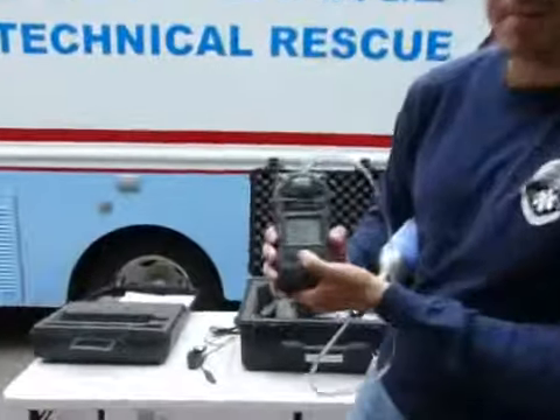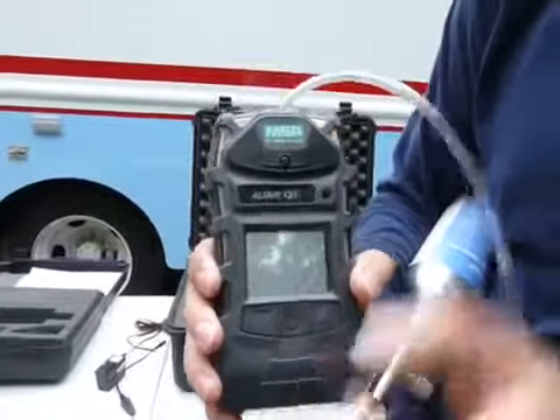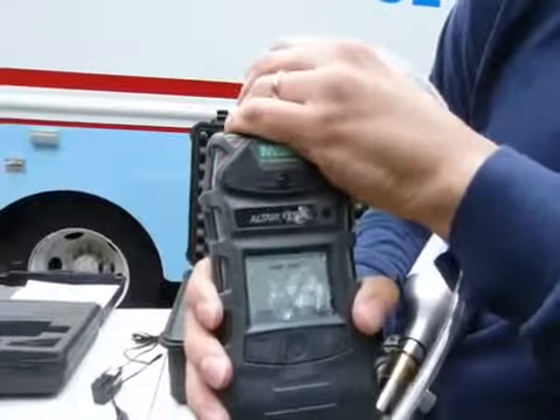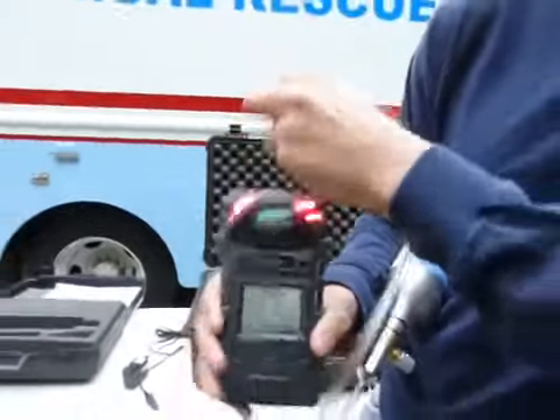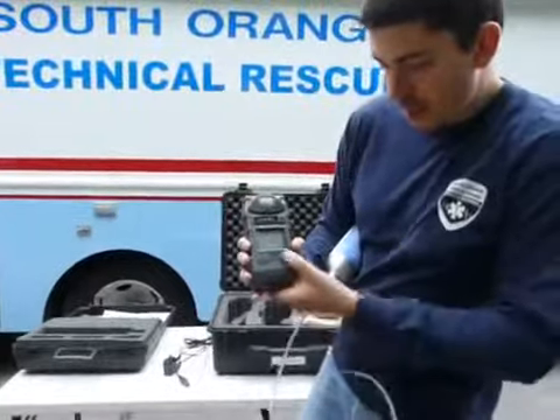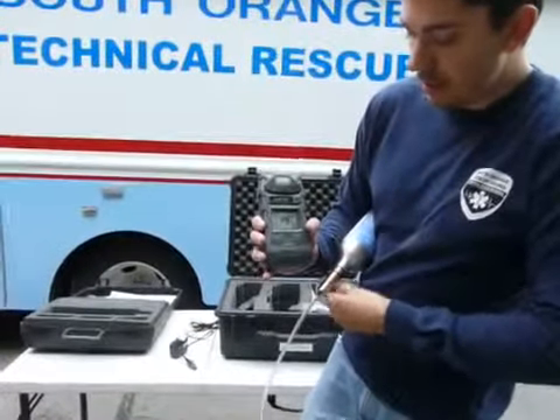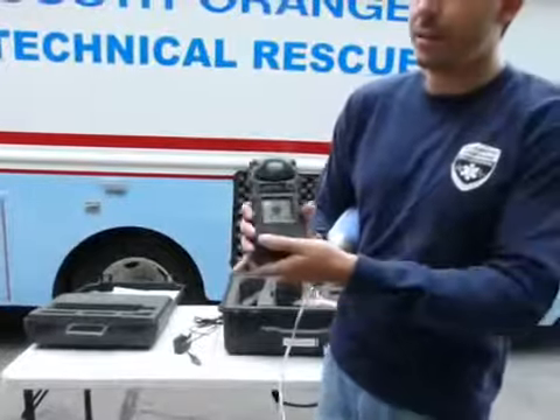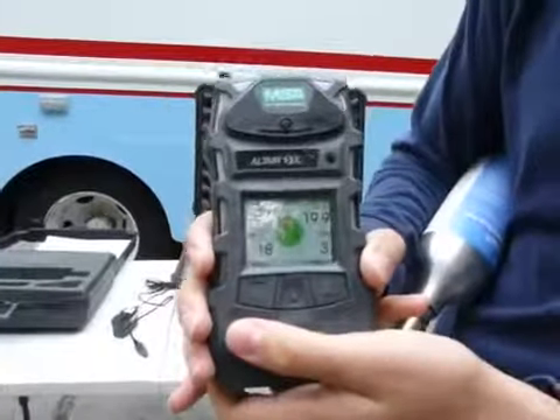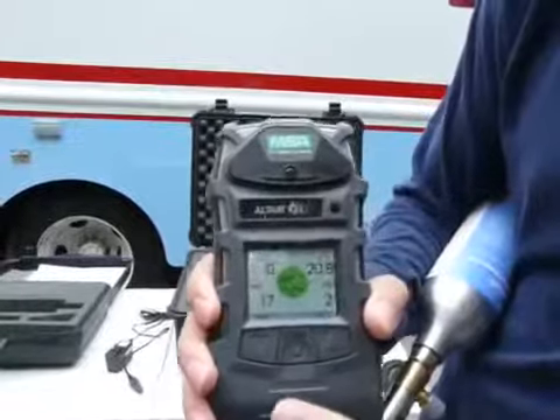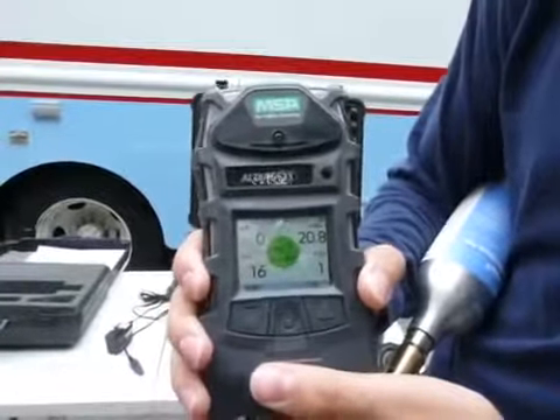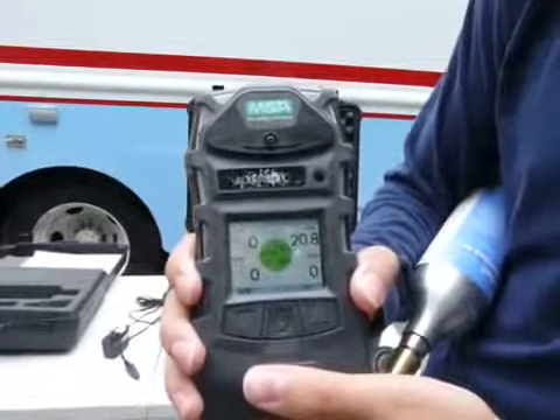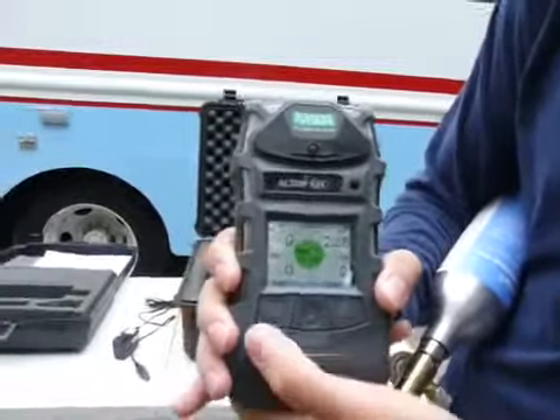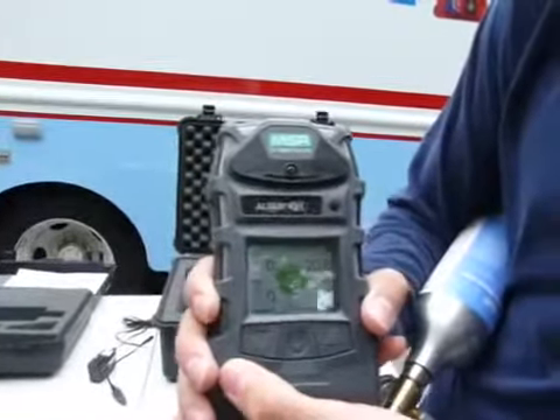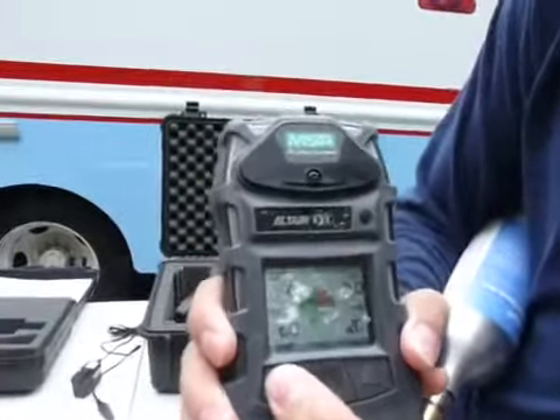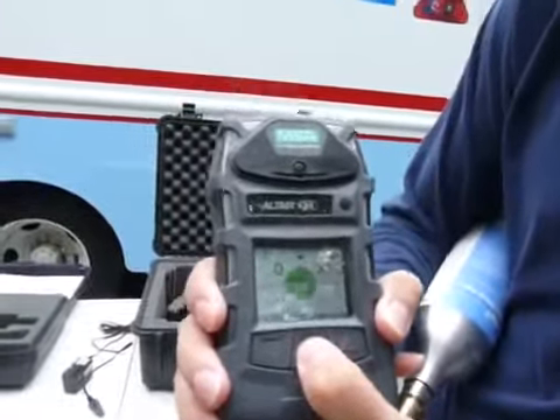Here again, we get check marks through each of the sensors. We know that everything is working properly. At this point, we can disconnect the calibration gas. We're going to reset those alarms. And here you can see, just in the general screen, these levels are all returning to normal because we've disconnected it from the calibration gas and it's exposed to fresh air. To scroll through each of the screens is simply the down arrow, and then to turn off, you hold down the power button.